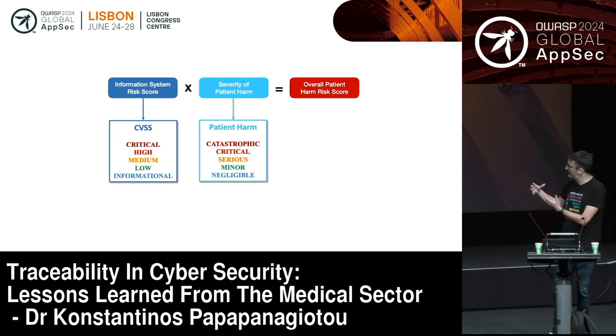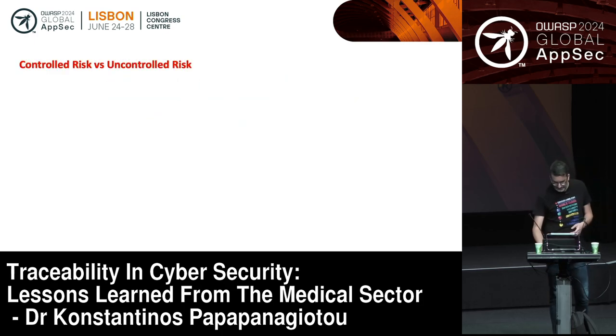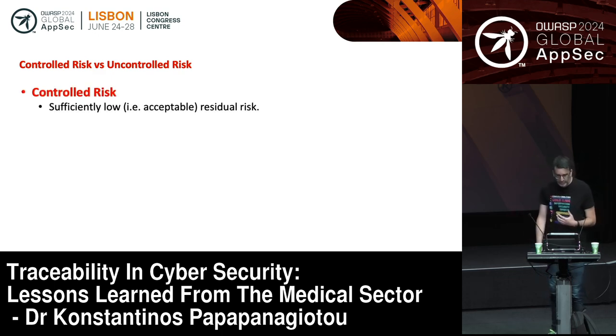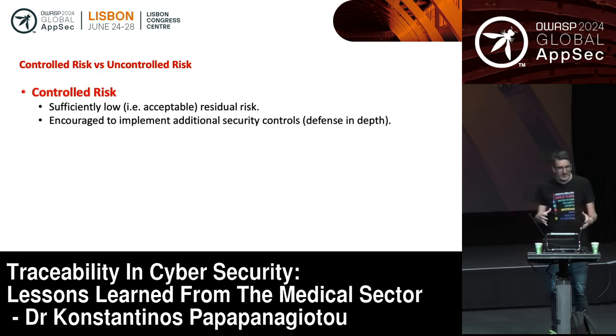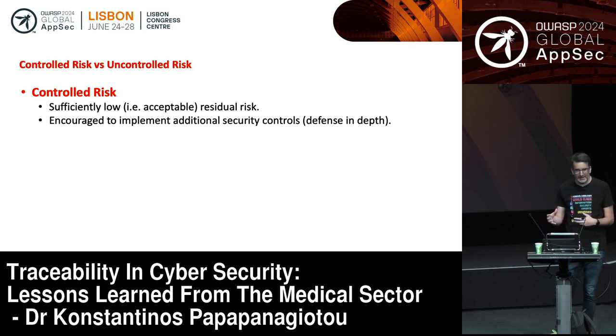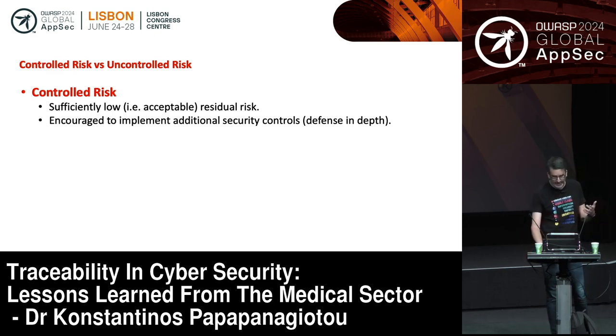And this is how we take into account the patient harm risk score. Once we do that, we have the concept of controlled risk and uncontrolled risk. Controlled risk means we have a low residual risk, things we can manage that do not result in serious harm. FDA still encourages us to implement additional security controls and do defense in depth, but other than that, it's okay to leave it as is.